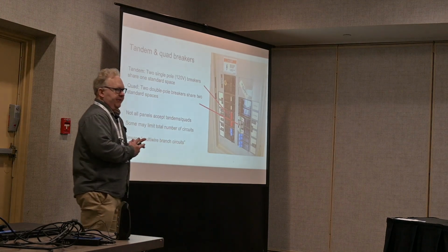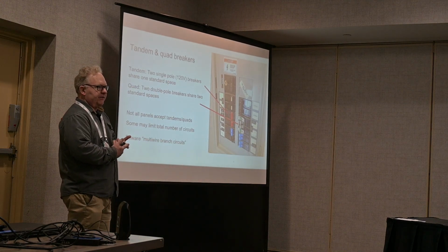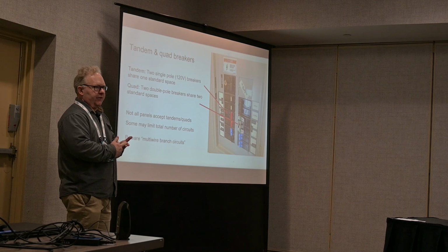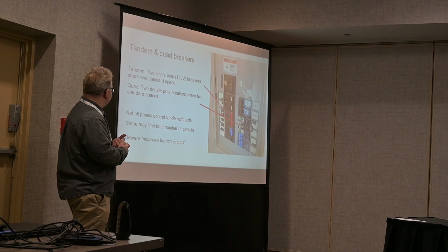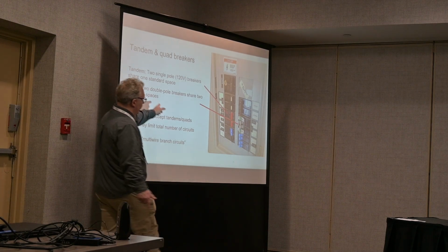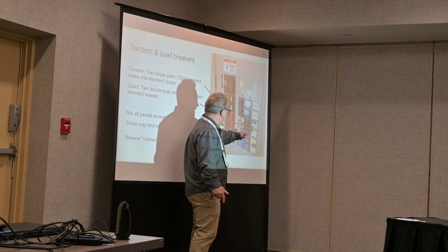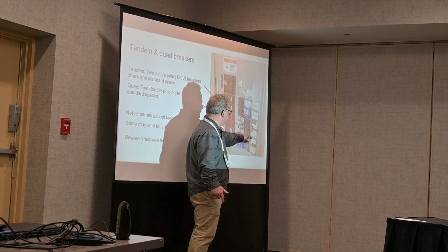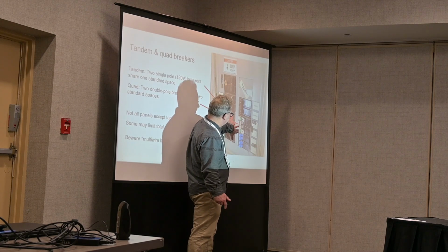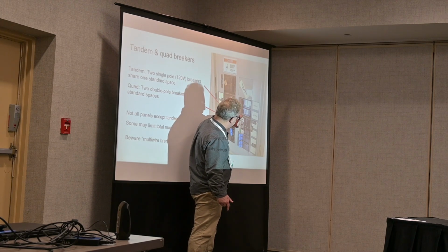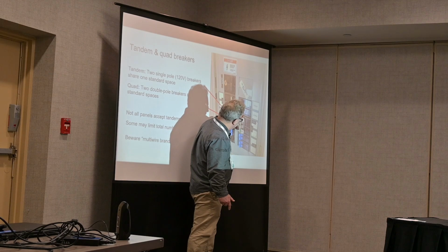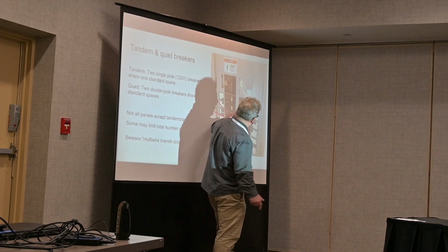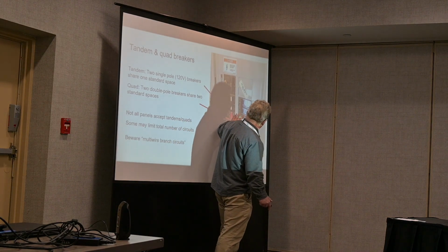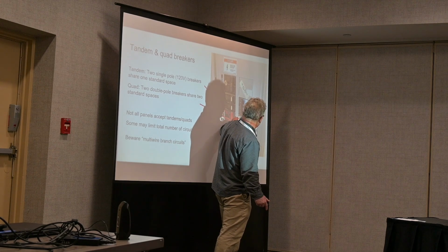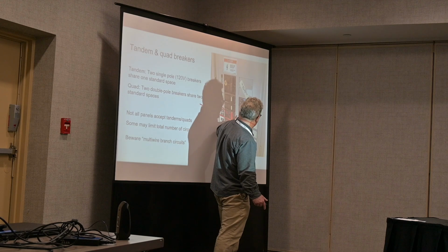Not all panels are going to accept tandem breakers, and some may set an upper limit on how many you can have. And there are also quad breakers, which are basically double tandem breakers for double pole circuits. So in this case, we've got a tandem breaker here. The green handles go to the clothes dryer, electric clothes dryer, and the gray handles go to the stove.